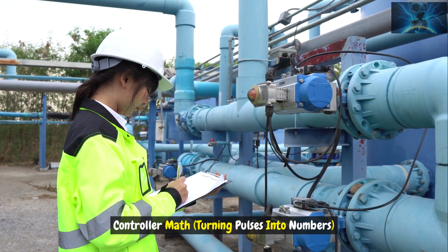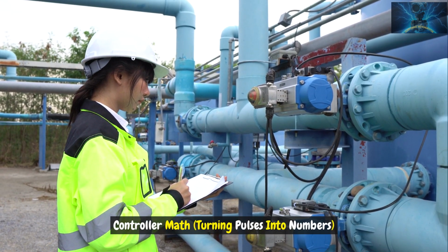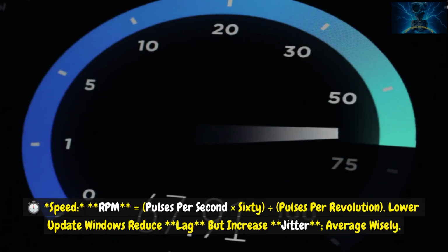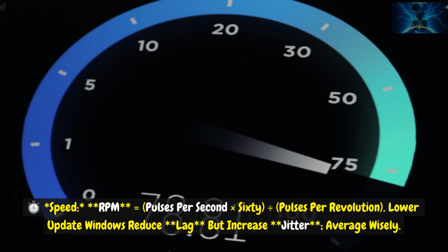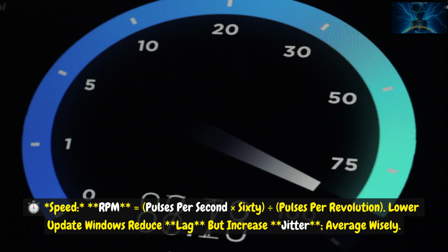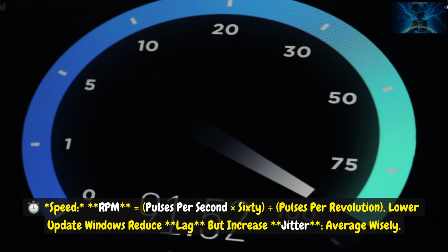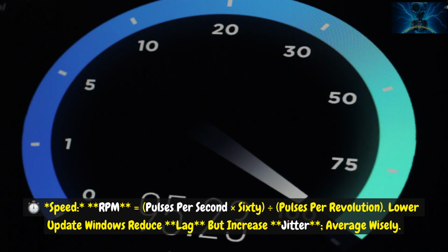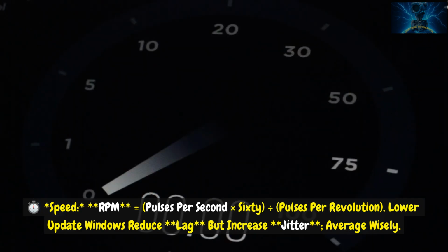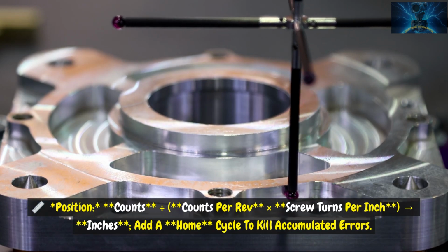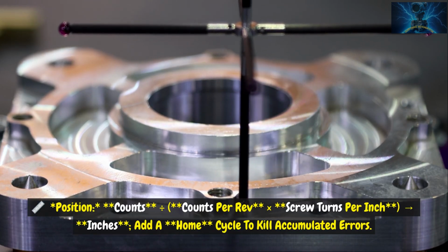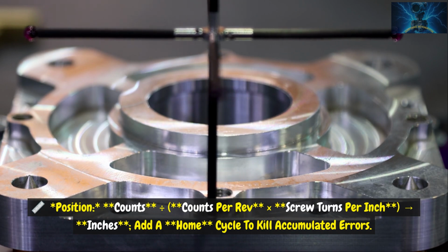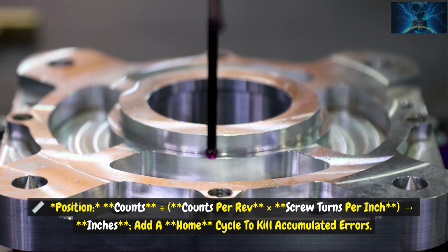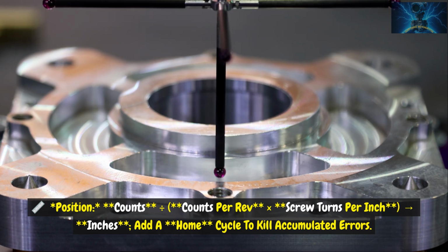Controller math: turning pulses into numbers. Speed in RPM equals pulses per second times 60, divided by pulses per revolution. Shorter update windows reduce lag but increase jitter, so average wisely. Position equals counts divided by counts per rev, times screw turns per inch, giving inches. Add a home cycle to kill accumulated errors.